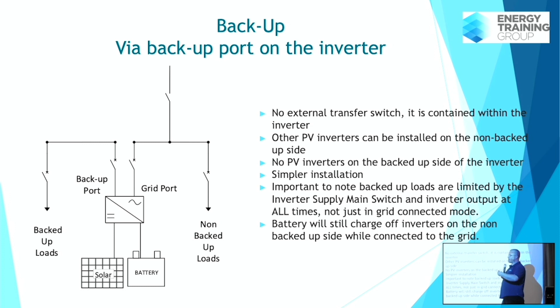The next thing I wanted to talk about is where we can install batteries. There are a lot of restrictions as to where you can install batteries. And I'm talking at the moment about Section 4 and 5 batteries. The restrictions are even greater if you do one of those Section 6 batteries that you have to assemble. The main things are that you cannot be within 600 mil of any exit or any side of a window or building ventilation that ventilates a habitable room, within 600 mil of any hot water units, air conditioning units, or any other appliance not associated with the integrated BESS.